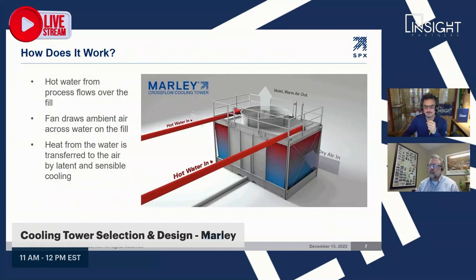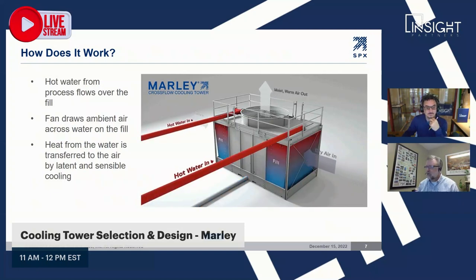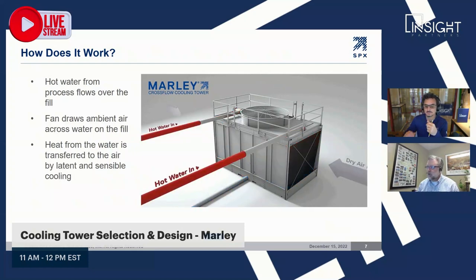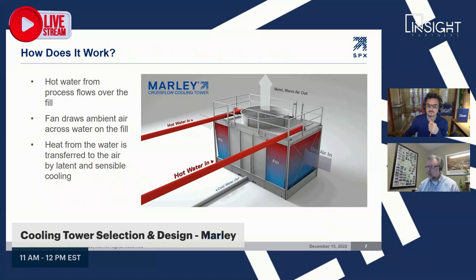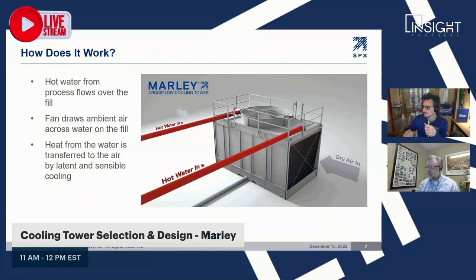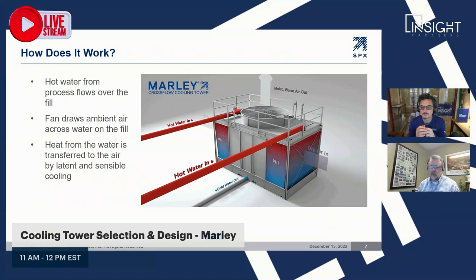How does the cooling tower itself work? You've got hot water coming from your process that gets distributed over our heat exchange media, which we call fill. At the same time, a fan draws cool, dry air into the unit. That air picks up heat and moisture, and then the fan discharges that moist, warm air at the top. Cold water is collected at the bottom of the tower in our collection basin and sent back to your process.